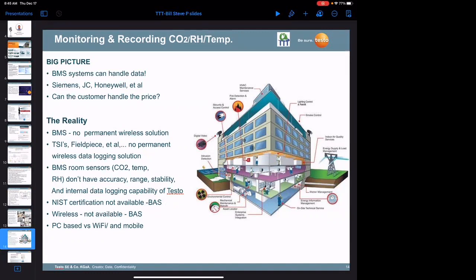Meaning I can display a nice consistent number, making people think the system is working fine. I can smooth out the output of those measured variables because they use a calculus-based program called PID control: proportional, integral, and derivative. Depending on how you vary those three points, you can smooth out the system's response so it looks stable, like it's working great. You don't want to do that for a life, health, and safety application like ASHRAE identifies here.